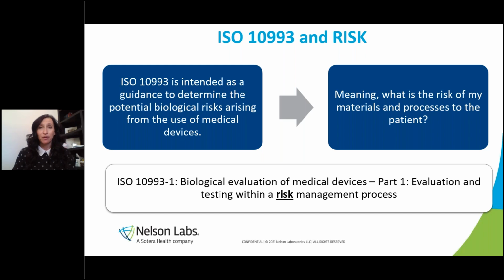So when we think about biocompatibility, I automatically think of ISO 10993. This is a series of standards that addresses biocompatibility and how we approach that. And ISO 10993 is all about risk. So the title says, evaluation and testing within a risk management process. So we need to think about what the risk of the materials and processing of the device are to the patient. And that's really what we're assessing.